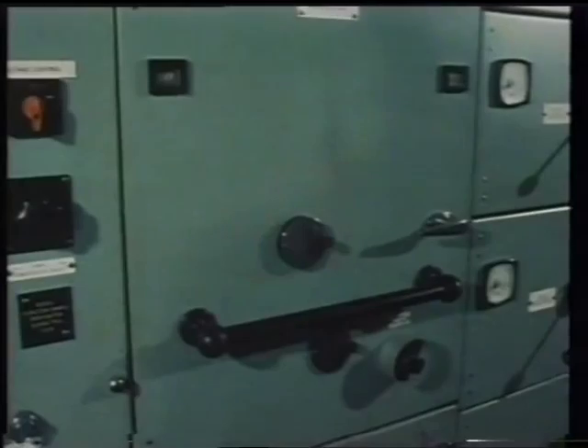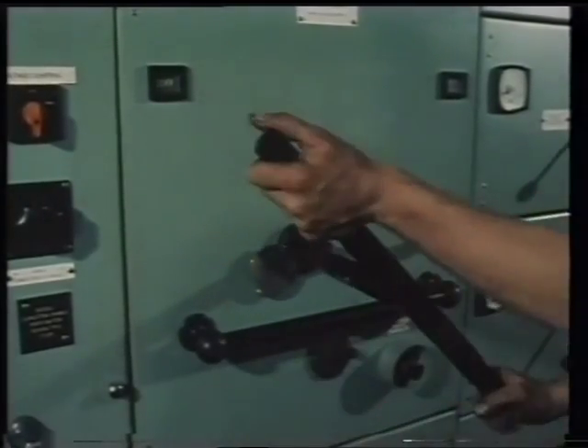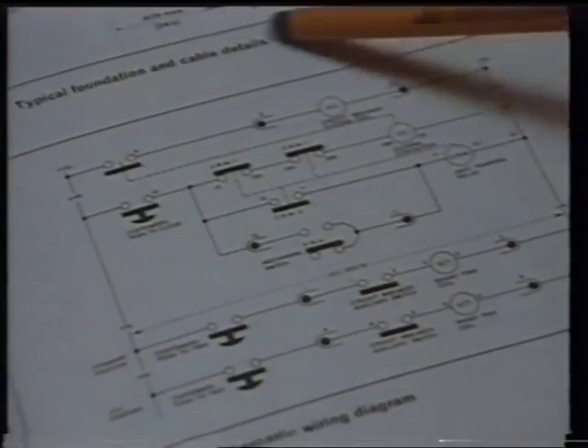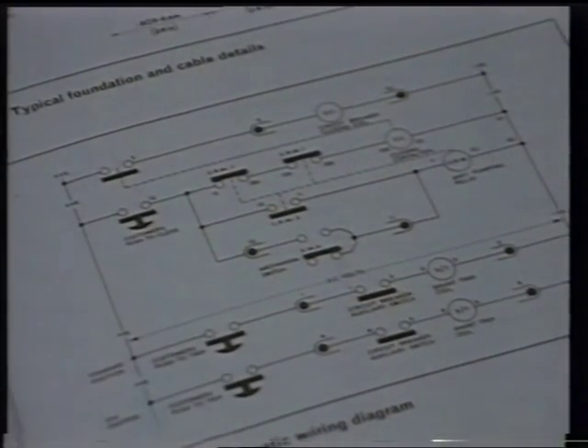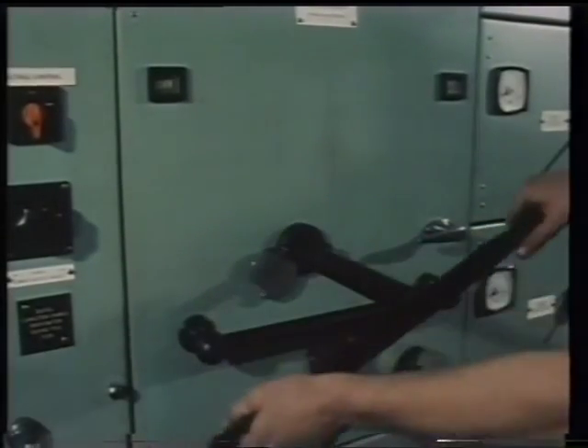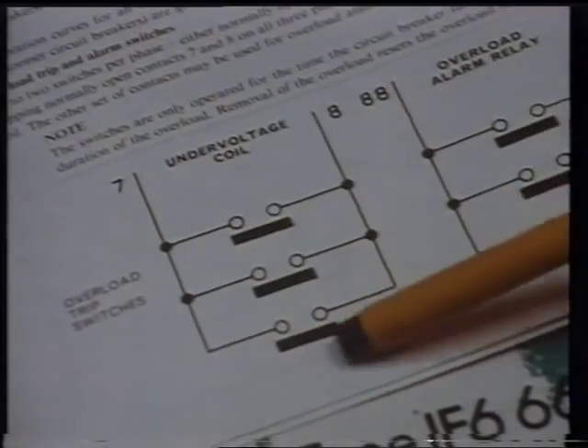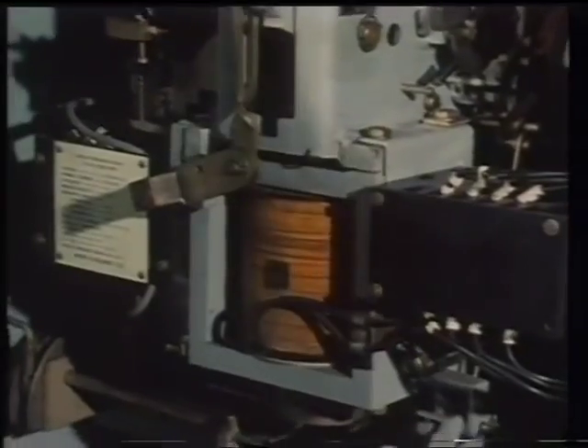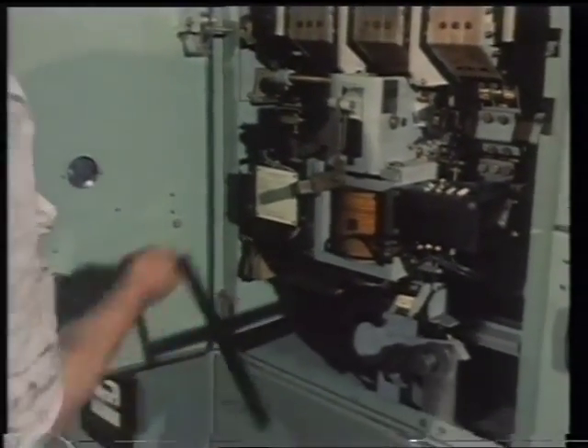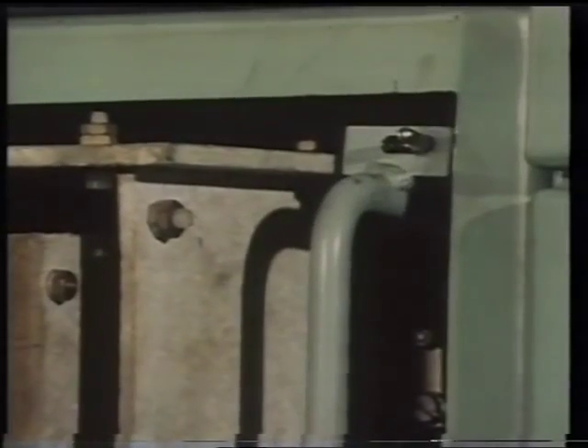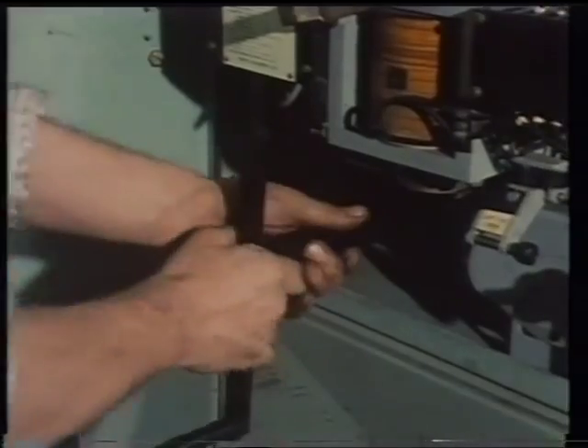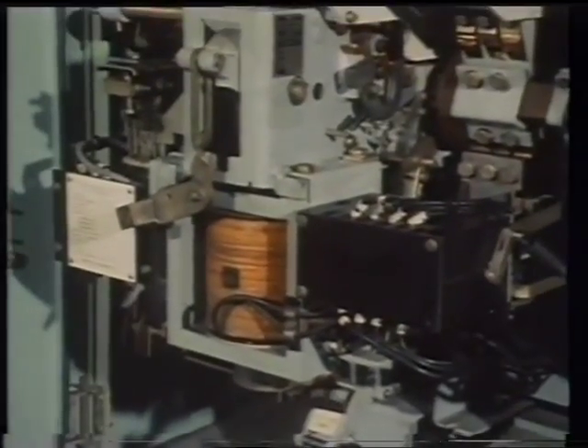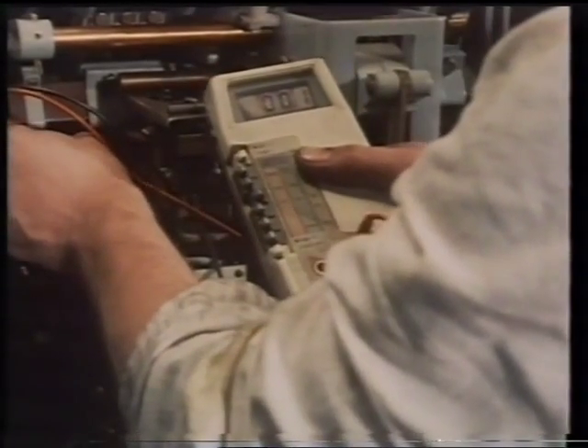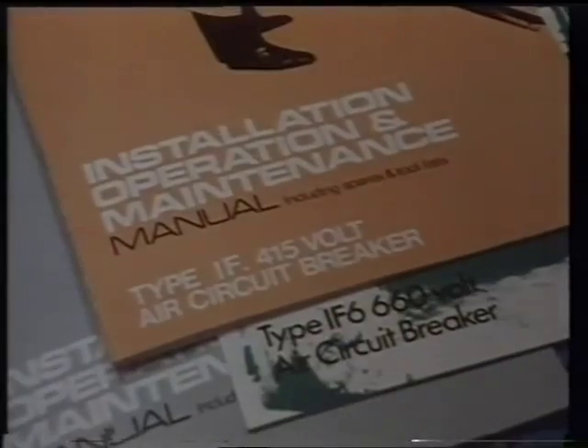If, for any reason, a circuit breaker does not function normally, first try and close it manually in the test position when it's safe to do so. If it closes and holds in, this indicates a fault in the closing coil circuit. If it closes but fails to remain closed, the no-volt coil circuitry may have a loose connection or other fault present, perhaps in the DC transformer rectifier unit. Withdraw the circuit breaker into the full-out position and disconnect the control wiring and plugs. Test the appropriate circuits for faults. Always test that the circuit is dead before testing for continuity. The manufacturer's diagrams must be consulted for checking the circuitry.